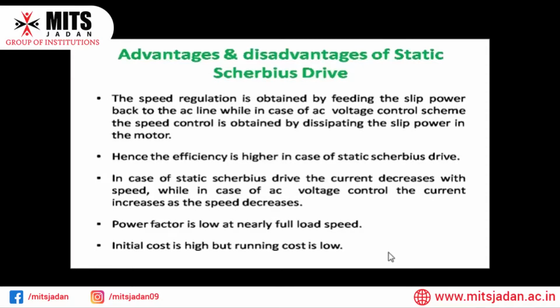Secondly, in the static Scherbius drive, the current decreases with speed, while in AC voltage control, the current increases as speed decreases. Then the power factor in this case is very low even at full load speed. For this type of drive, the initial cost is high, but the running cost is very low.